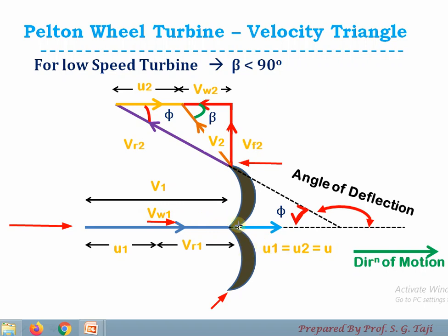Since V1 is shown at the inlet point, the relative velocity can be calculated as velocity of jet minus velocity of bucket — that is Vr1 = Vw1 − U1 = V1 − U. After striking at the splitter, the first component at the outlet is Vr2, the relative velocity. If the bucket is smooth and frictionless, relative velocity at inlet equals relative velocity at outlet, so Vr2 = Vr1. Vr2 makes an angle phi with the direction of motion, where phi is the outlet tip angle, generally varying between 10 to 15 degrees.